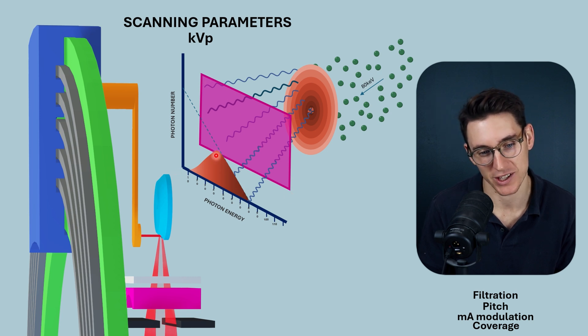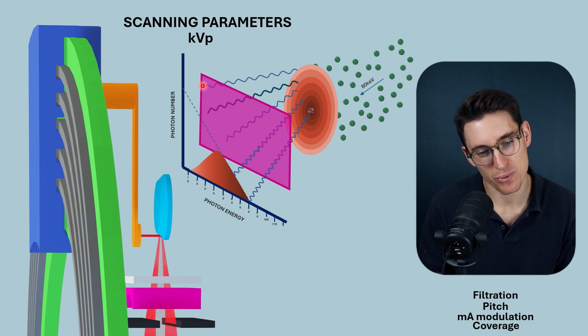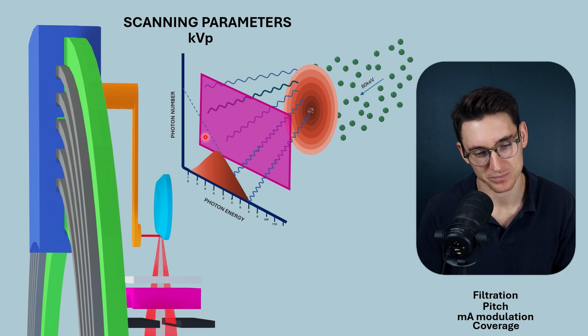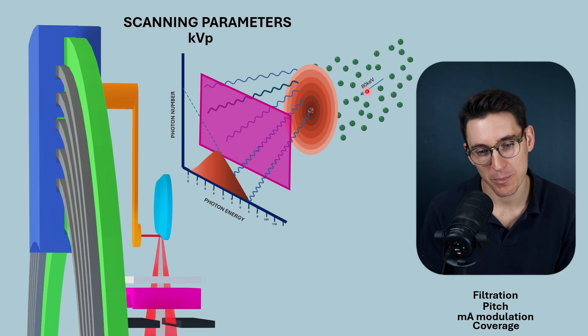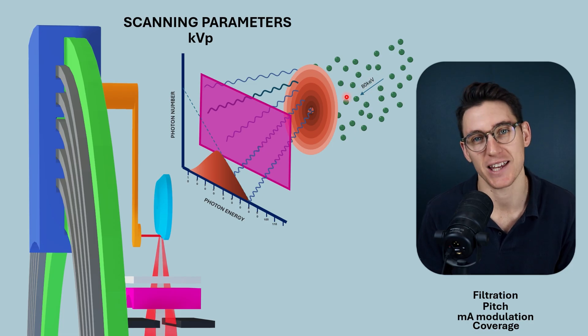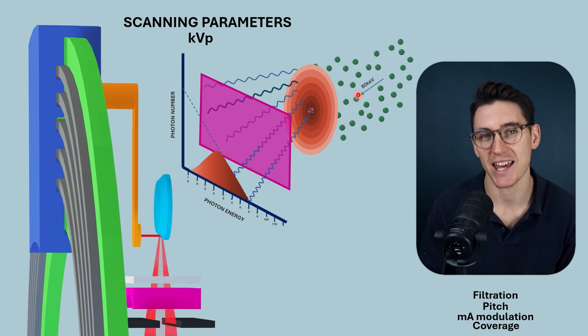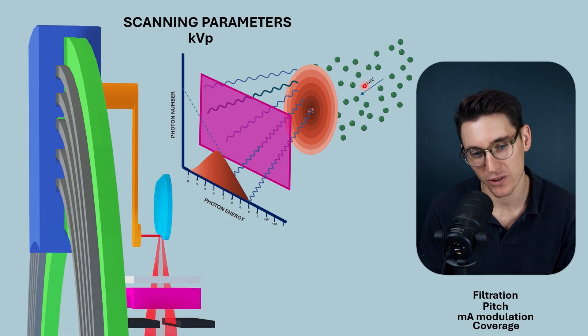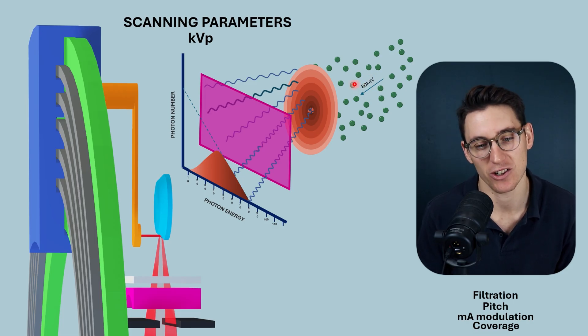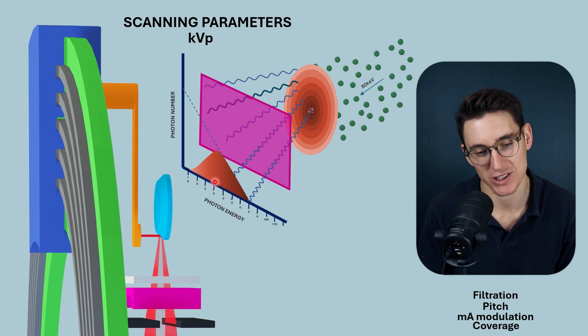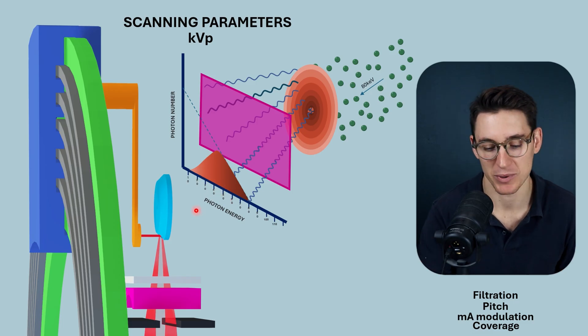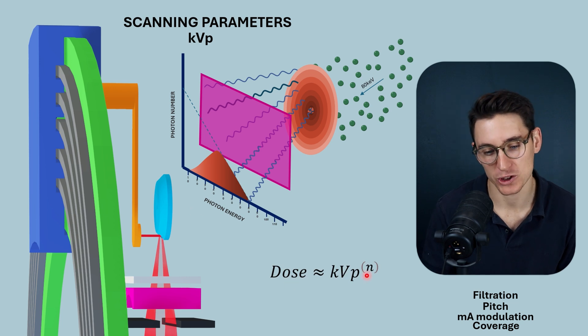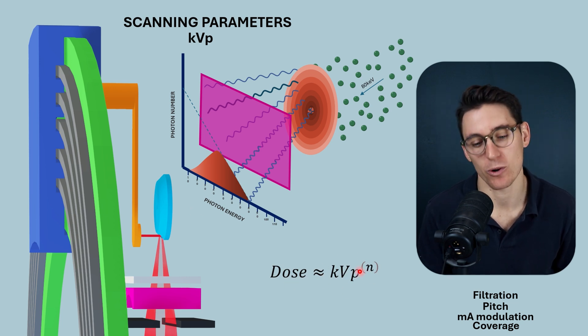We've seen this diagram before. The electrons create x-rays that form a spectrum. This purple block here is a filter that preferentially filters out the lower energy x-rays. So we get our x-ray spectrum heading towards the patient. What happens if we were to increase the KVP? Increasing the KVP is going to increase the number of electrons and the average energy of those electrons, and as a result, it's going to influence the x-ray spectrum. Importantly, dose is related to KVP.